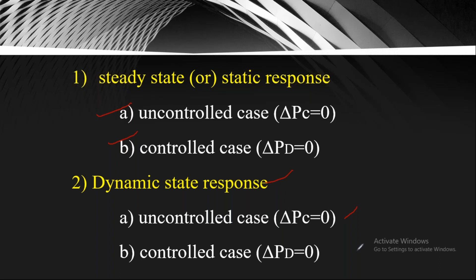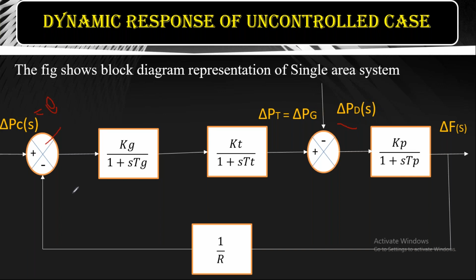Right. So this is the reference block diagram of the single area system, and it has three modeling systems: the speed governing model, the turbine model and the generator model, with the feedback of regulation 1 by R. This is a representation of the single area system. Now from this block diagram we have to derive the transfer function for the uncontrolled case. In this uncontrolled case, based on our assumptions, the speed changer value should be equal to 0, and we have to consider only delta PD. So when it is 0, there is no need to consider this summation parameter, right? Now let me see what the block diagram becomes after assuming delta speed changer is equal to 0.